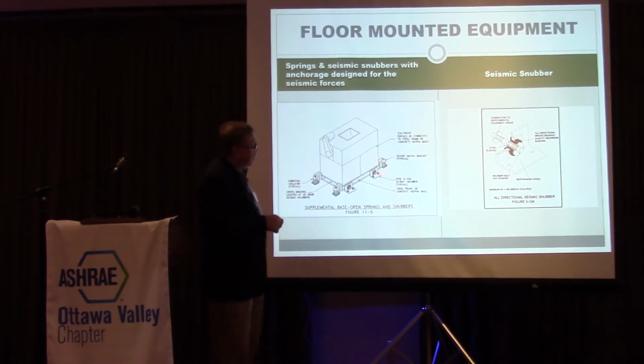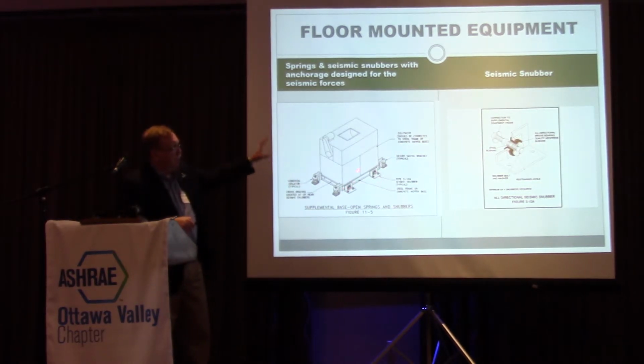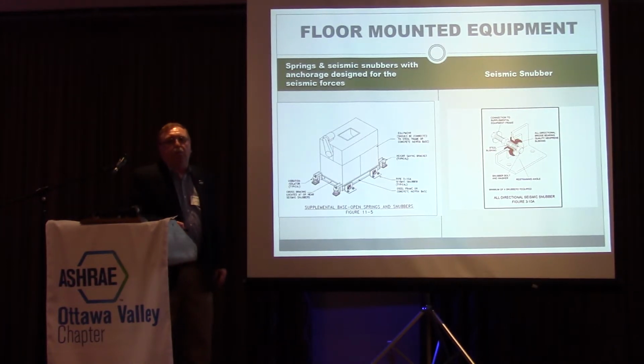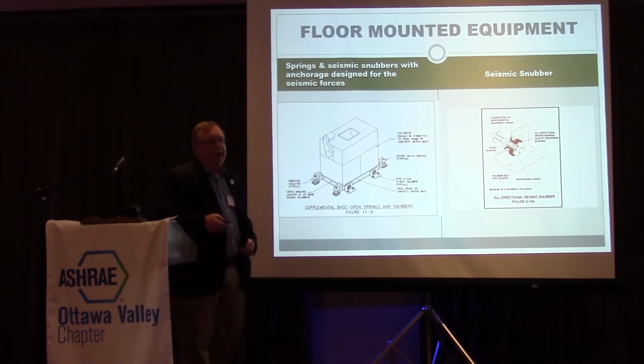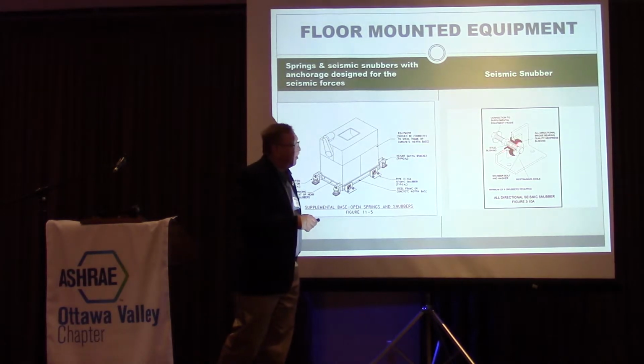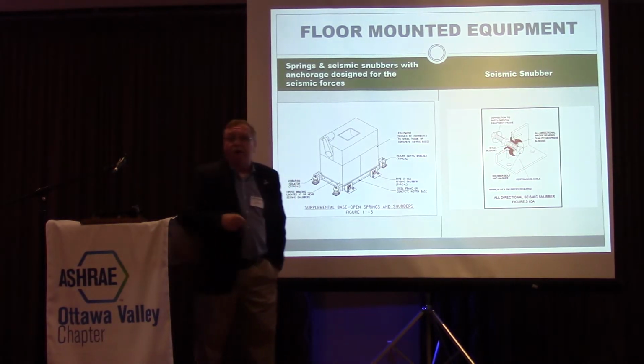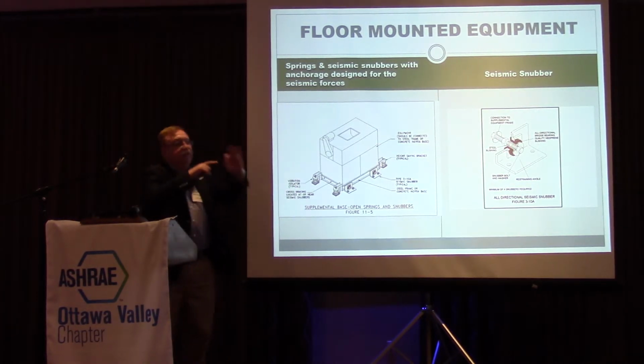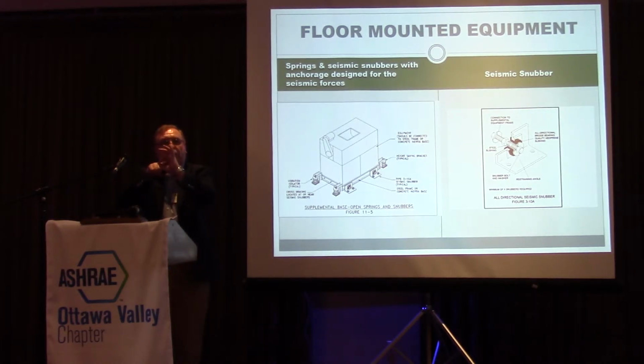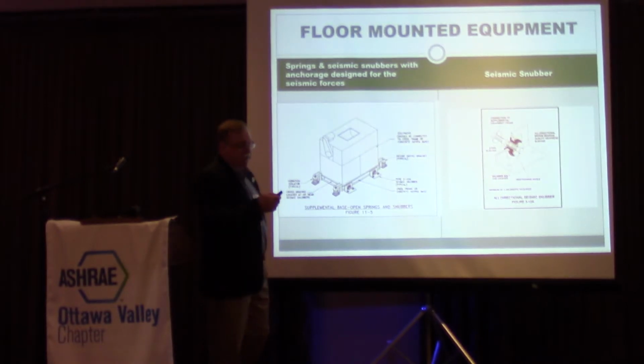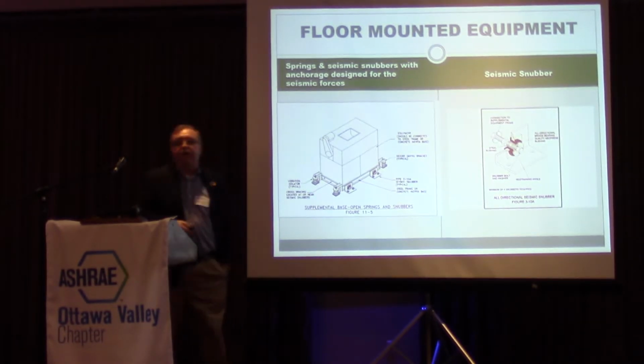During day to day operation while this thing's running, that bolt is in the center of that rubber washer, but it has an air gap around it, usually between 3/16 to 1/4 of an inch of airspace. So all day long it's fine. Now the earthquake comes, hits one side, hits the other side, whatever. It can only move that 3/16 of an inch, and that's it. It holds it in place. These are very effective snubbers, they work very well.